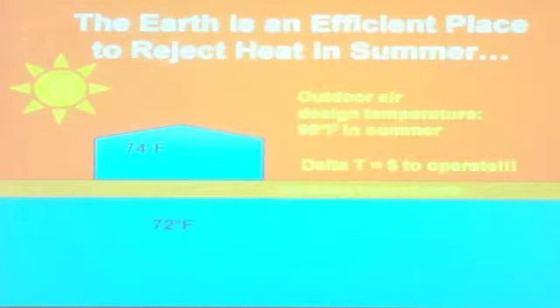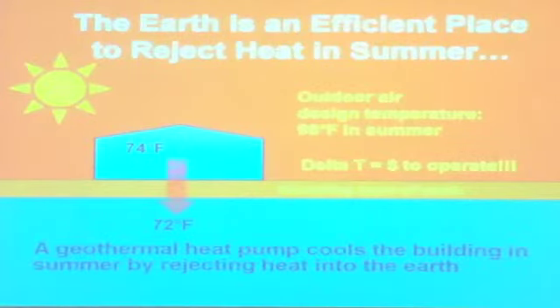So you see here that the earth is 72 degrees, the building is 74 degrees. The bigger the temperature difference that you're trying to bridge, the more it costs you to operate. So the higher the delta T, the higher the operating dollars. Go to the next one. So by going from a 74-degree building to a 72-degree earth, it'll cost half as much as it would going from a 74-degree building to a 98-degree air outside.